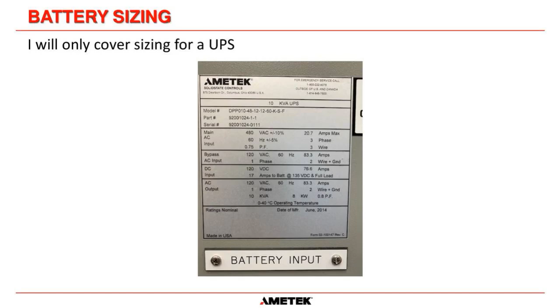what I'm going to do is basically use a kVA rating to get you where you need to be. So a 10 kVA inverter with a 0.8 power factor can only produce 8 kilowatts of real power. That's the first thing a lot of people get confused about. You have to size it at the 8 kilowatts, not at the 10 kilowatts. We do sell systems that have a 10 kVA, 10 kilowatt output, but most systems are rated at 0.8 power factor. And also remember, we don't live in a perfect world. Inverters are not 100% efficient. For our DPP, which is our pulse width modulation inverter, it's roughly an 88% efficiency rating. So we have to work backwards.